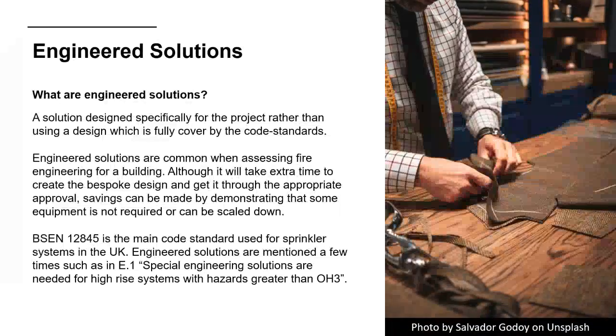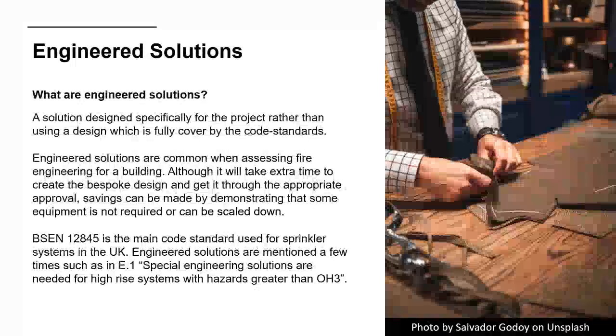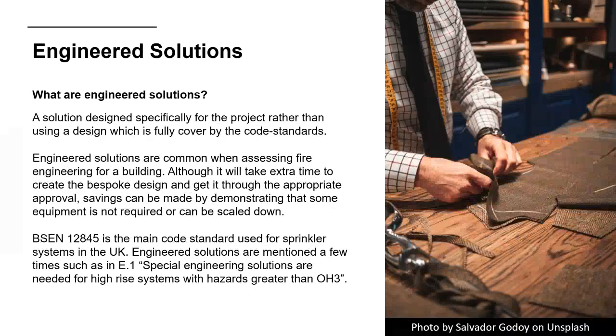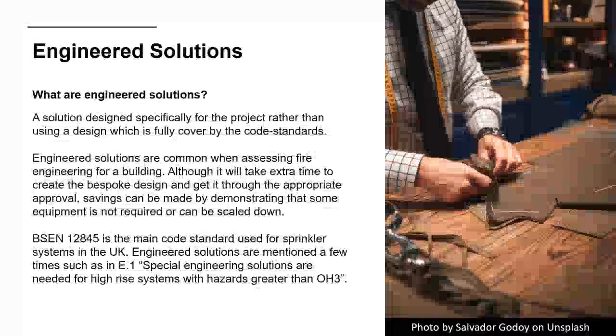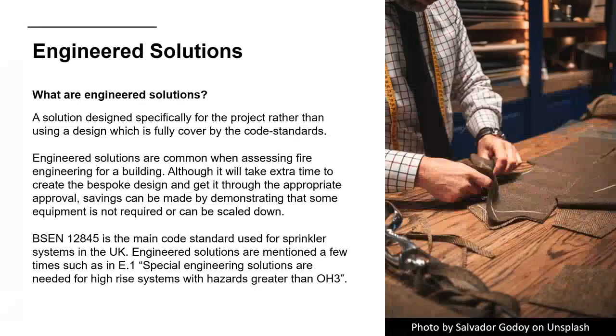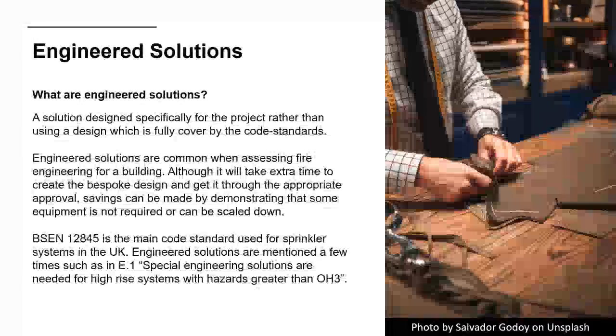BS EN 12845 doesn't mention engineered solutions much, and I suppose why would it, because it's the code standard, so it's expecting you to follow it to the letter. But it does mention it a couple of times, and here's one example. In Annex E.1, it says special engineering solutions are needed for high-rise systems with hazards greater than OH3. So it's quite clearly saying this standard does not specifically cover high-rise systems with hazards greater than OH3. If you've got high hazard and high rise, BS EN 12845 is saying we don't cover that - it's not saying you can't do it, but you'd need a special engineering solution to cover it. So that's an example of an engineered solution.